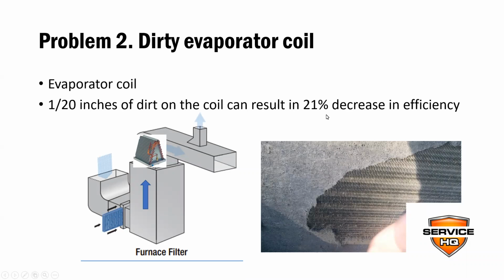Now, this is that same picture we showed you earlier. This is an upflow furnace. So on this particular example, the coil sits on top of the furnace and the air is coming in. It passes through the filter, passes through the furnace, passes through the evaporator coil, which is where the entire refrigeration process takes place. And then the air is delivered to each room in your home. So if this thing gets a coat of dust on it, you can imagine what that does to your airflow in your house.